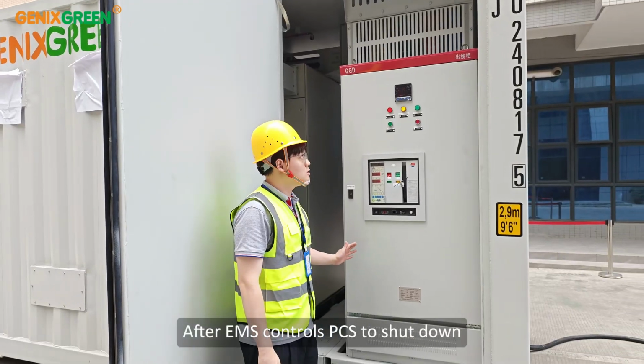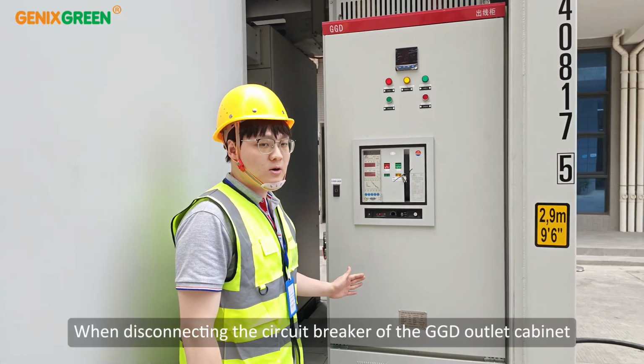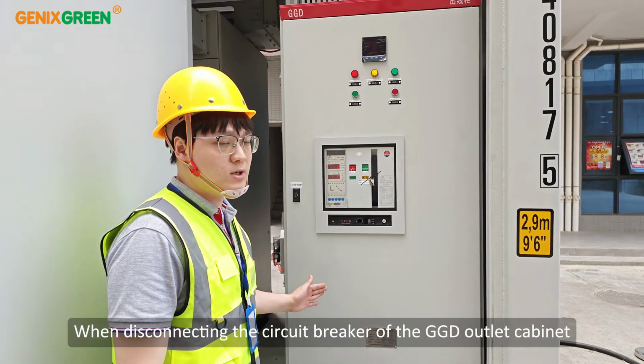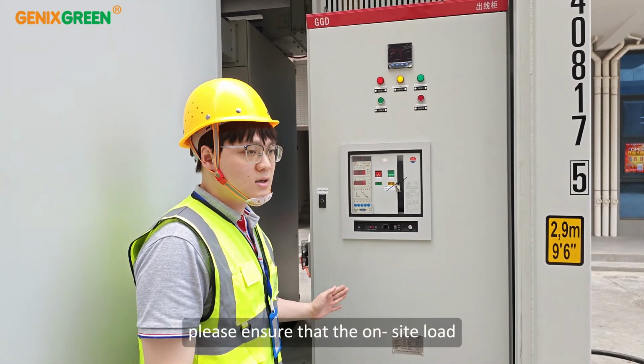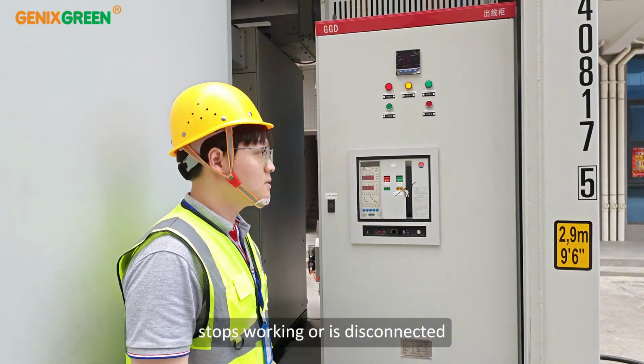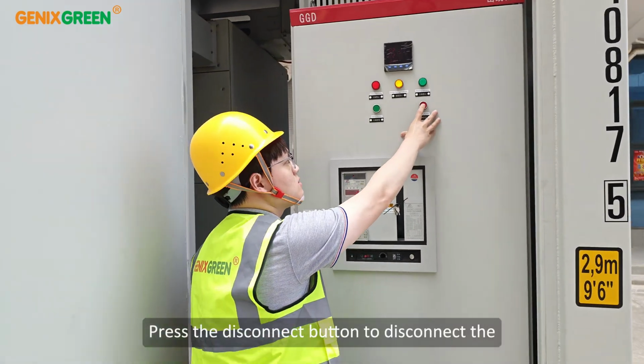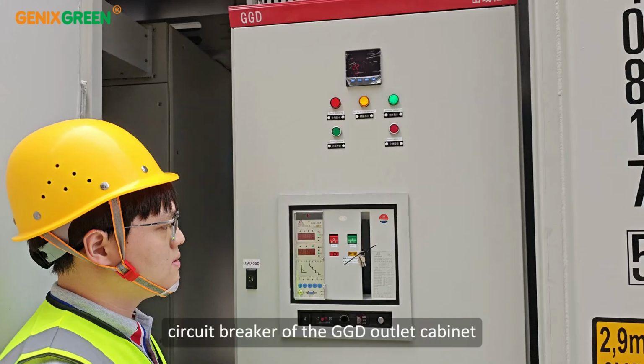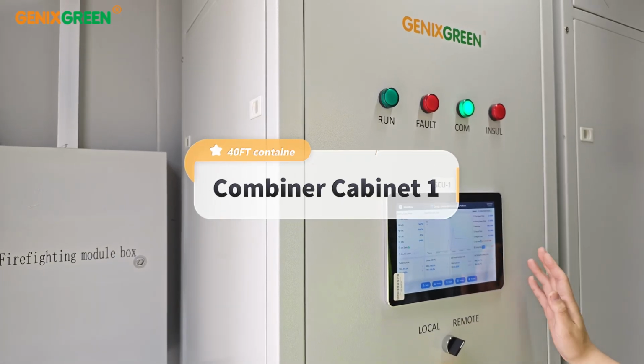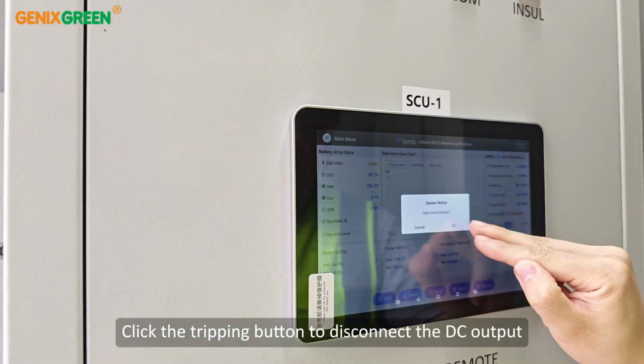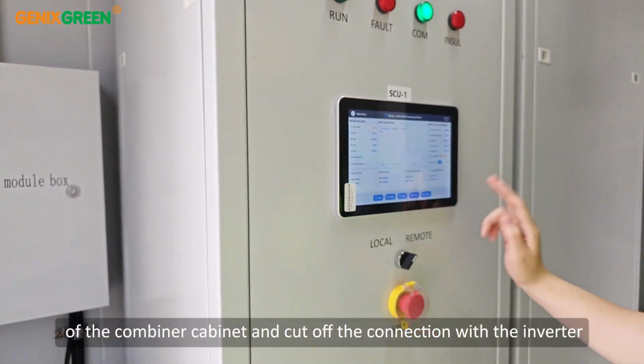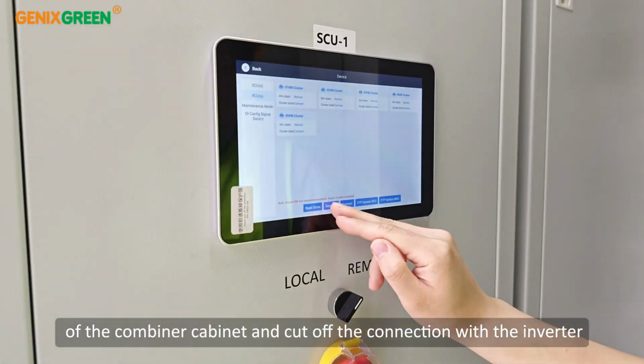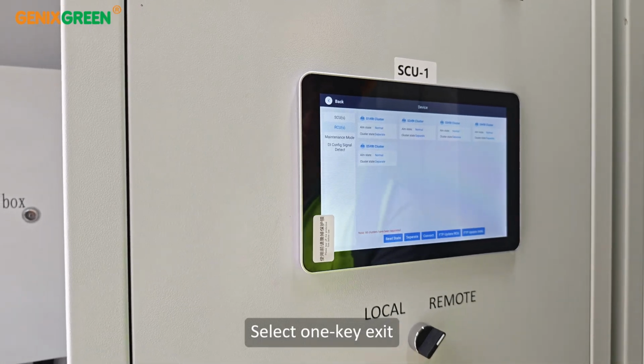After EMS controls PCS to shut down, when disconnecting the circuit breaker of the GGD outlet cabinet, please ensure that the on-site load stops working or is disconnected. Press the disconnect button to disconnect the circuit breaker of the GGD outlet cabinet. Click the tripping button to disconnect the DC output of the combiner cabinet and cut off the connection with the inverter. Select one key exit.